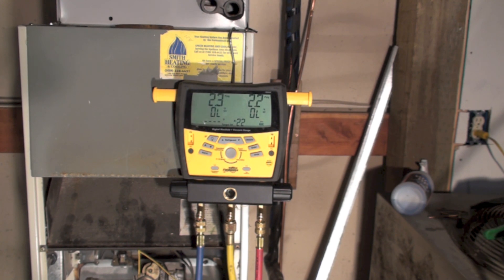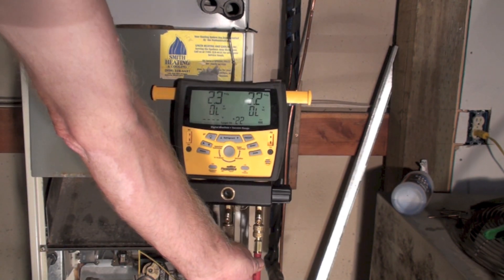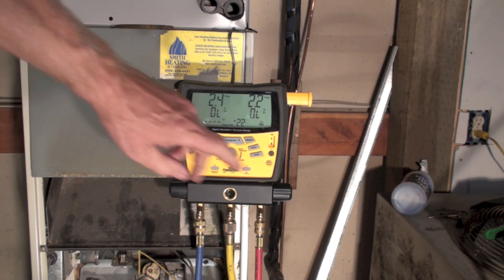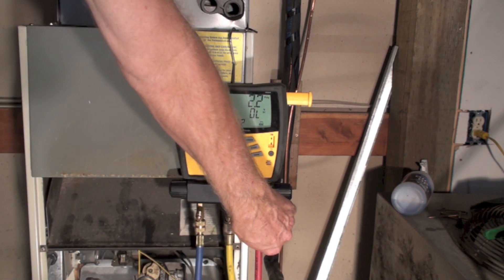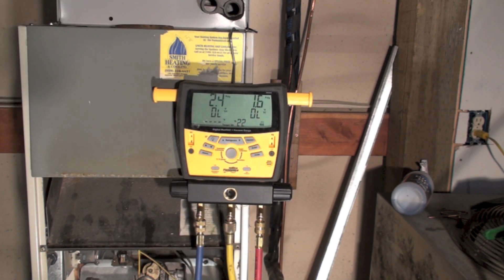So to make sure that I don't have any problem with air in that refrigerant line that I just put the Schrader in, I'm going to open this again, maybe a little more than a half second because the pressure is really low, but I still have positive pressure in the system.